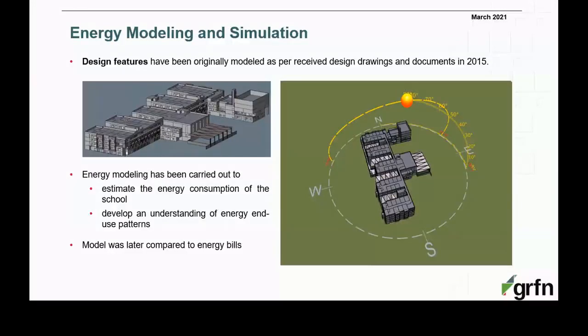So we've done the energy modeling. I mean, we did have some input into the design, but it was almost a detailed design. We couldn't change, let's say, the shape of the building or window to wall ratio. These things were already done, but we did improve a little bit on the efficiency of the HVAC systems. We've used, in this case, CIBSE, as can be seen from the model. And later, when the building was built, we did a comparison between the energy consumption that we got from the model and the energy bills, and we found that the patterns were very similar.